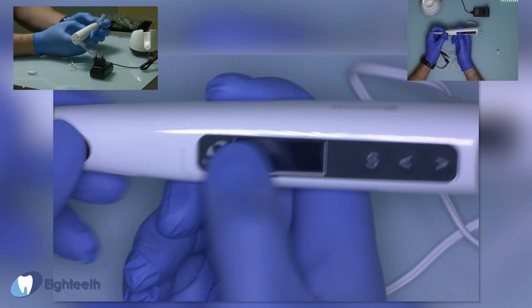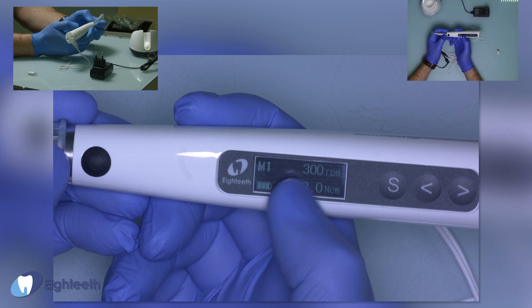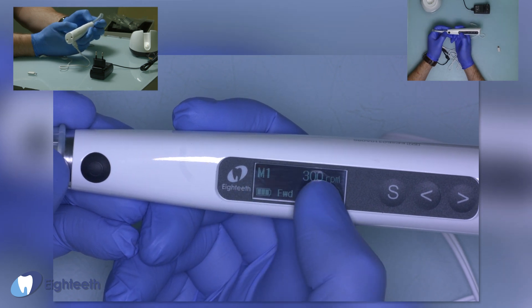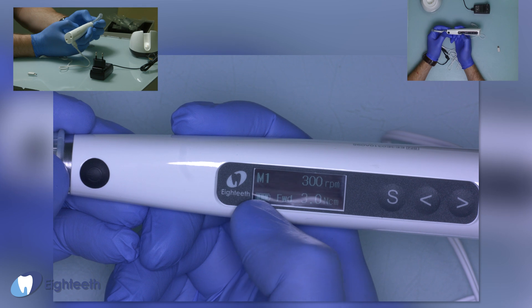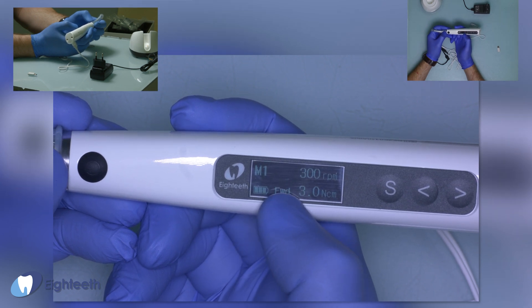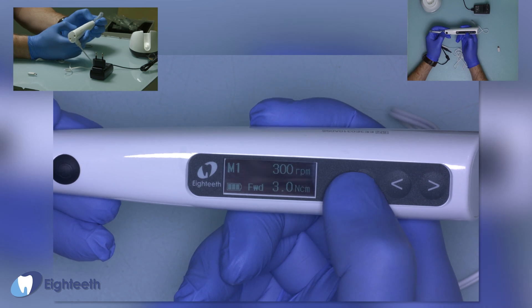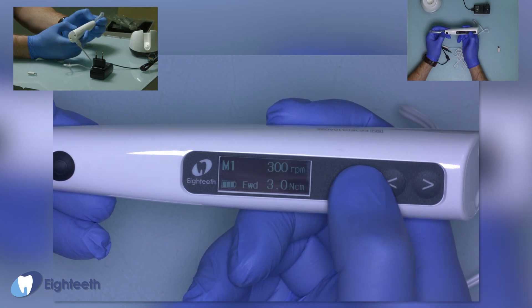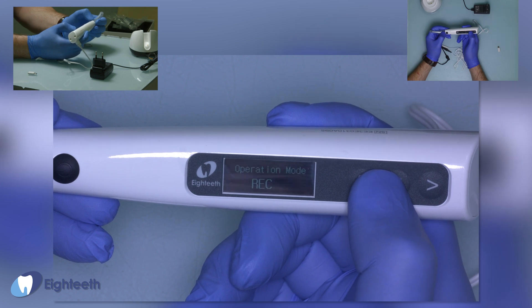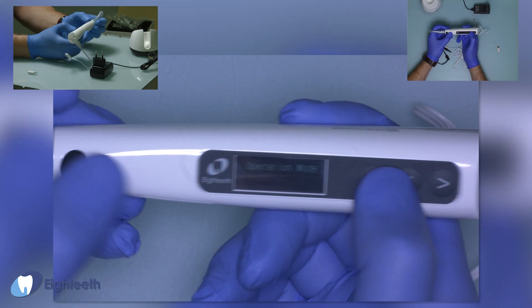Let's start the motor. Soft pressing of the start button — once the motor is ready, the display shows the program number, speed, power, battery level, direction (forward or reverse), and the torque. We also have one setup button and two changing buttons. The operation modes available are: forward, automatic, reciprocation movement, and reverse.